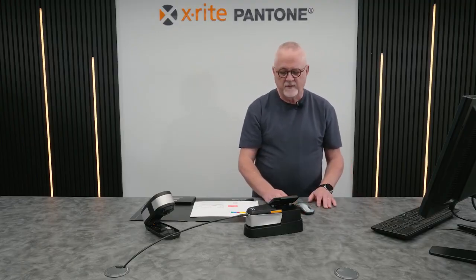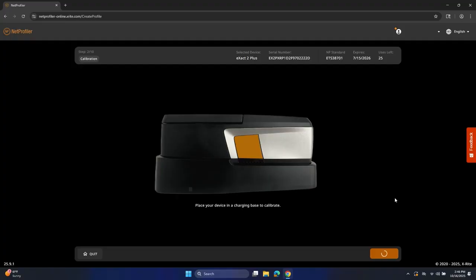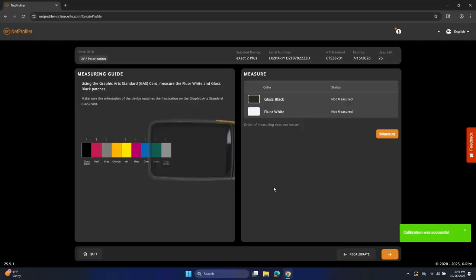We're going to wait a second while the device says calibrating in yellow on the screen. It says calibration complete. Once it knows that that calibration is complete, it moves on automatically. So it tells me calibration was successful, and I'm ready to go to the next step. So it's put it into targeting mode, and it says, using your graphic art standard card, measure the fluor white and gloss black patches. So it's actually showing them with an overlay of the instrument on top of them.